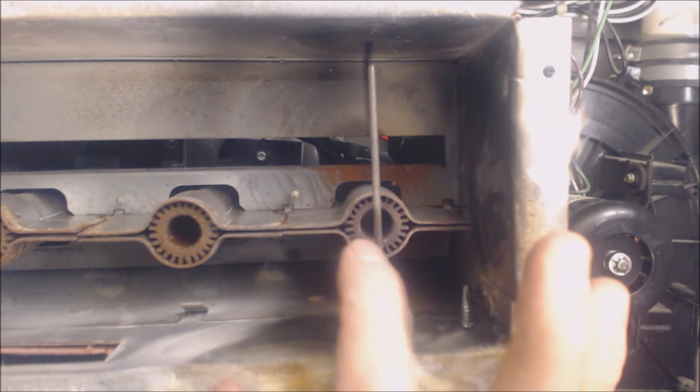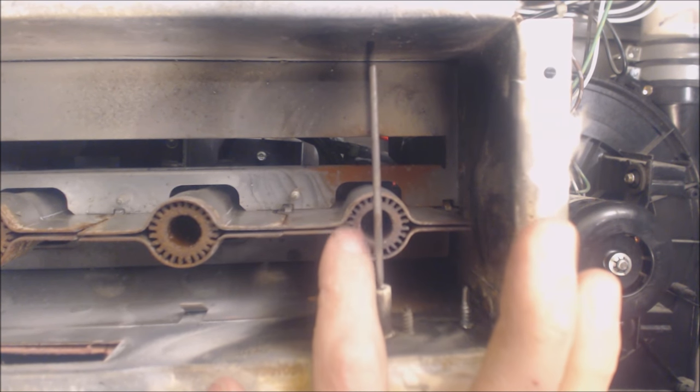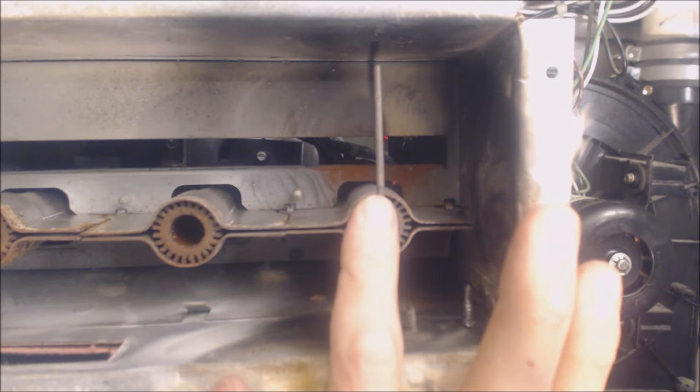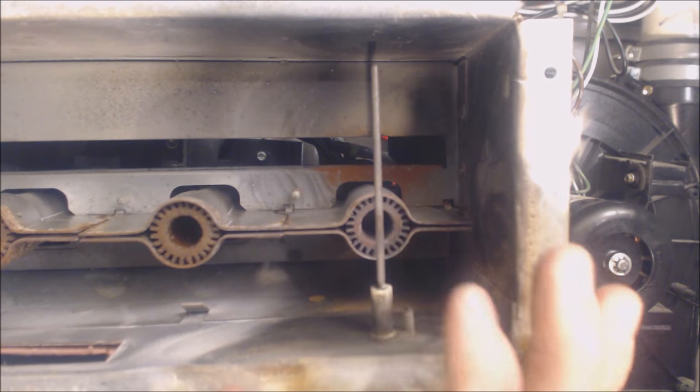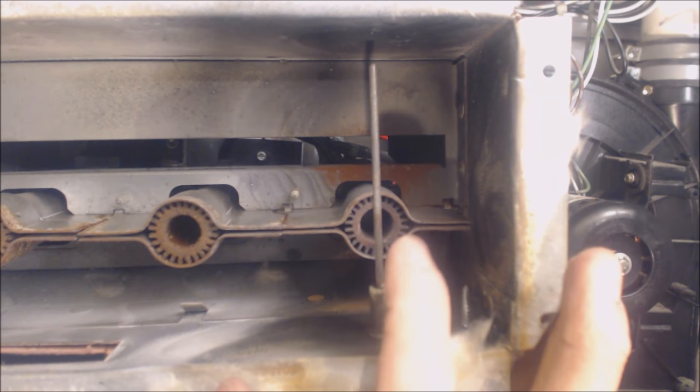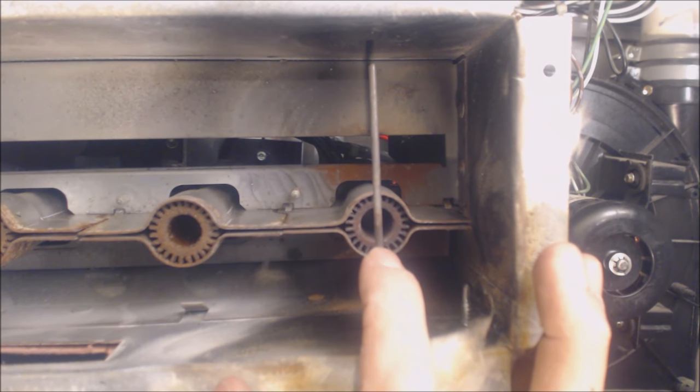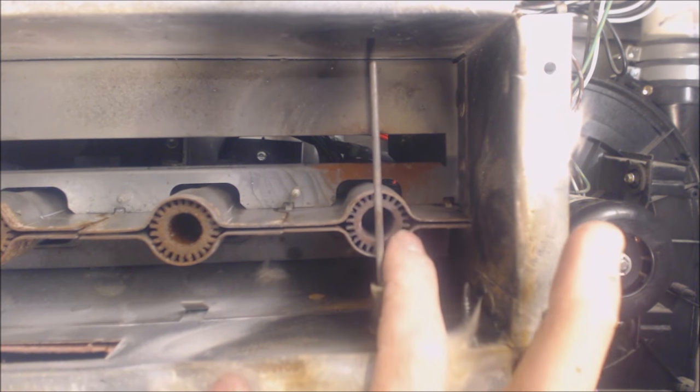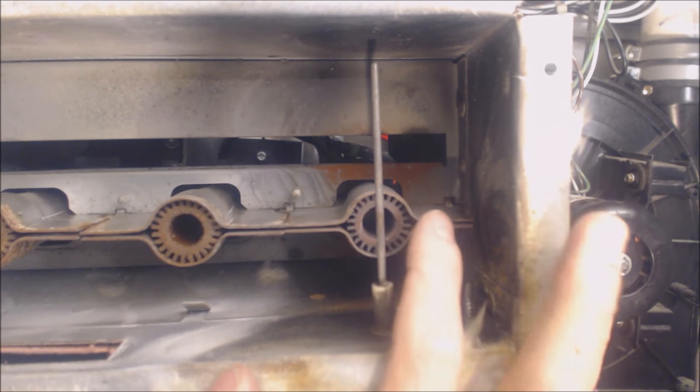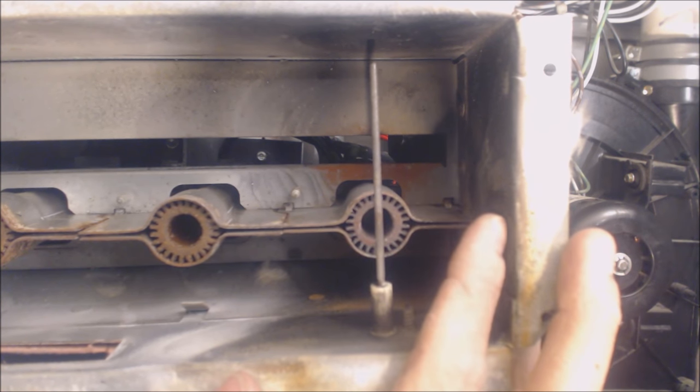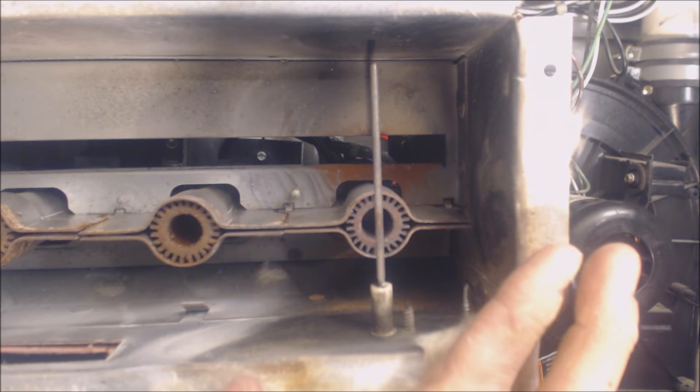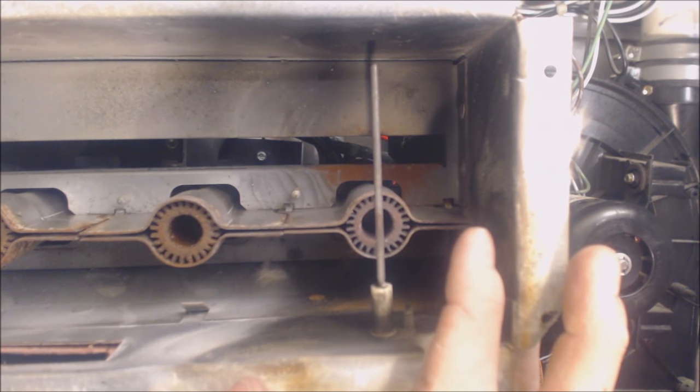And more electrons are being attracted to this head than coming back onto this rod right here. Now this rod needs to be about one fifth or smaller, the size of this burner retention head in order to get the proper micro amp reading. Most manufacturers have agreed on that.